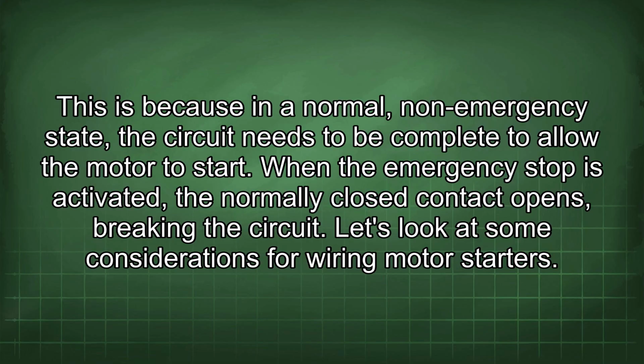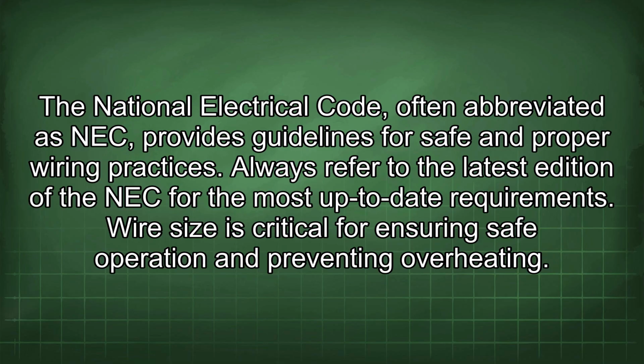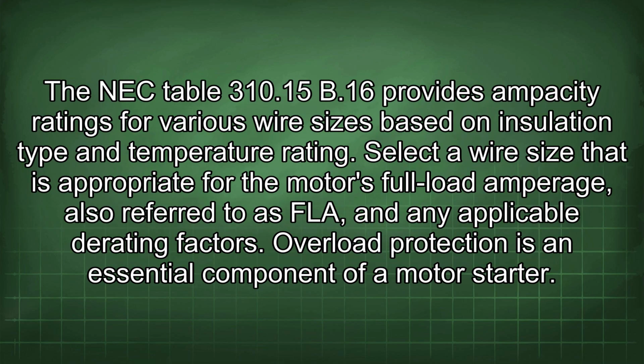Let's look at some considerations for wiring motor starters. The National Electrical Code, often abbreviated as NEC, provides guidelines for safe and proper wiring practices. Always refer to the latest edition of the NEC for the most up-to-date requirements. Wire size is critical for ensuring safe operation and preventing overheating. The NEC Table 310.15(B)(16) provides ampacity ratings for various wire sizes based on insulation type and temperature rating. Select a wire size that is appropriate for the motor's full load amperage, also referred to as FLA, and any applicable derating factors.